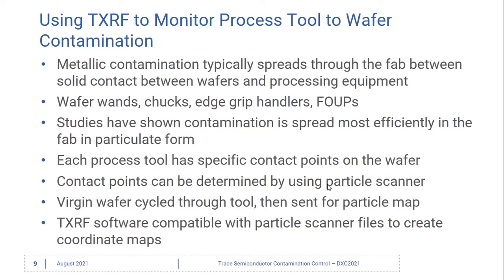edge grip handlers, chucks — the mechanical pieces of the equipment that can transfer contamination. Studies have shown that this contamination is spread most efficiently in particulate form. These particles can flow through the fab and transfer from the tools to the wafers at these specific contact points. Each processing tool has its own contact points with the wafer.